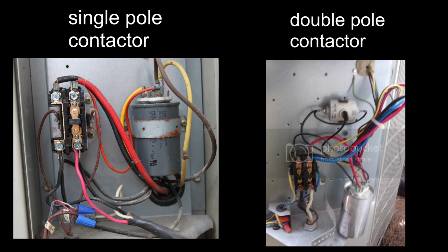The reason why this is a single pole is that on the left side, it has direct feed from the high voltage coming from the home. So basically, it's allowing one side of that contactor to be energized, where the other side does not energize and engage until it is actually calling for cool. If you notice on the right hand side, you'll see the little platform in the middle, a little metal black emblem, a little copper tab. That's where it pulls the contact to complete the circuit of the high voltage, and it runs all the way through, and then the condenser itself will engage.